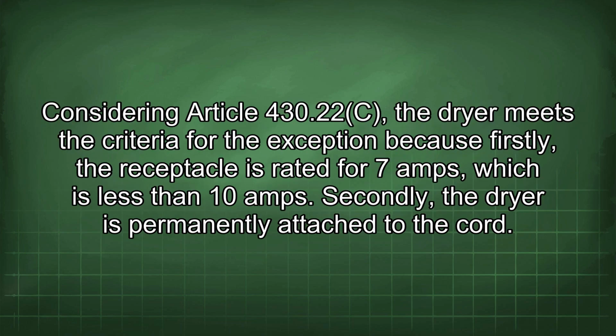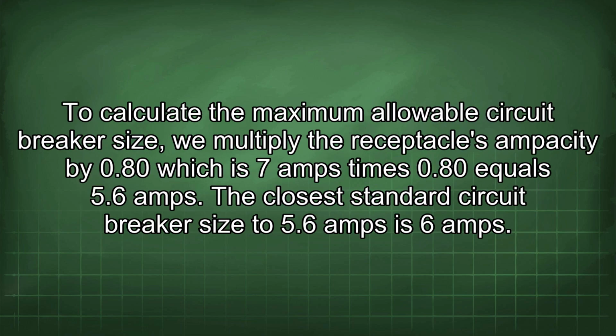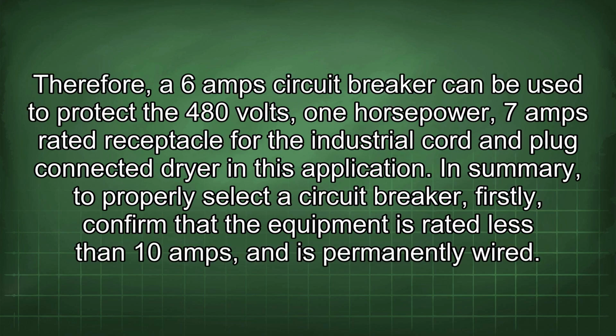Considering Article 430.22(C), the dryer meets the criteria for the exception because, firstly, the receptacle is rated for 7 amps, which is less than 10 amps. Secondly, the dryer is permanently attached to the cord. To calculate the maximum allowable circuit breaker size, we multiply the receptacle's ampacity by 0.80, which is 7 amps times 0.80 equals 5.6 amps. The closest standard circuit breaker size to 5.6 amps is 6 amps. Therefore, a 6 amp circuit breaker can be used to protect the 480 volts, 1 horsepower, 7 amps rated receptacle for the industrial cord and plug connected dryer in this application.